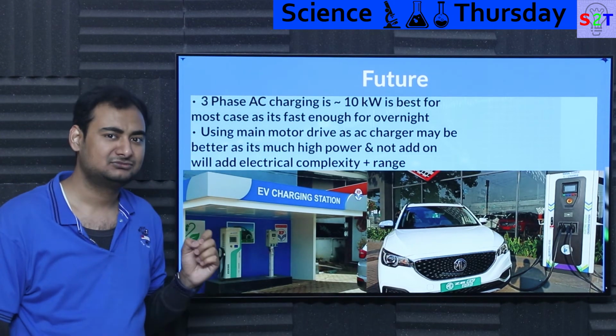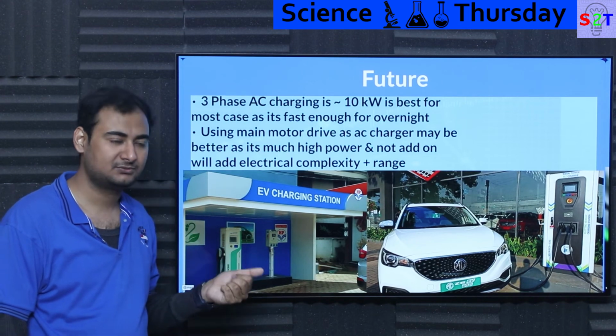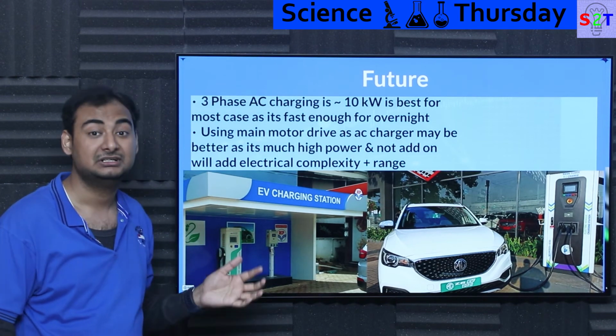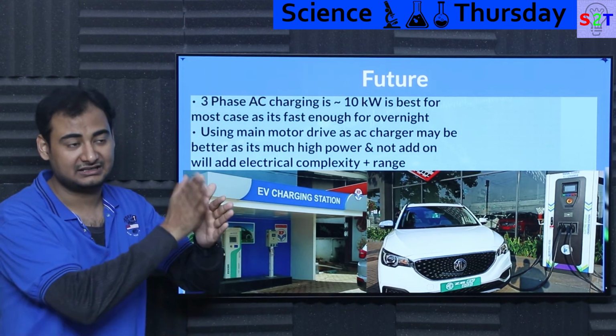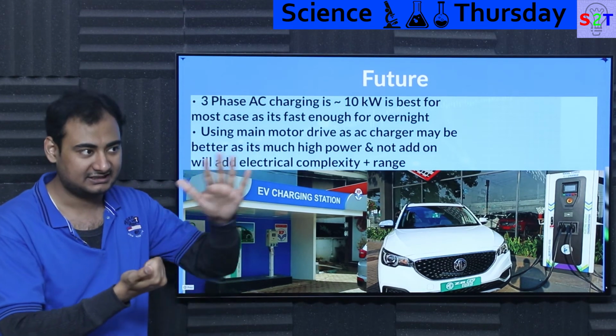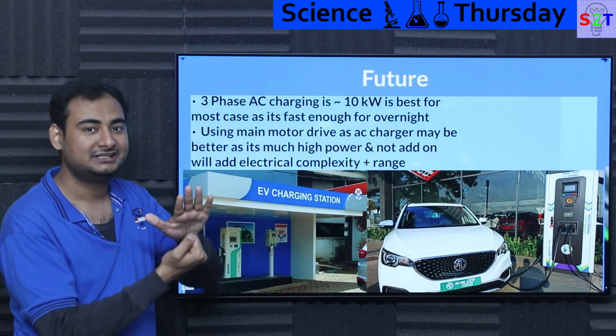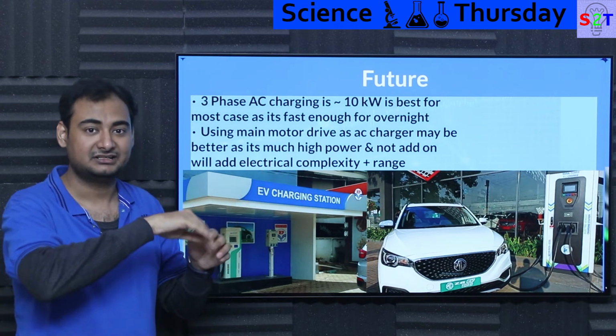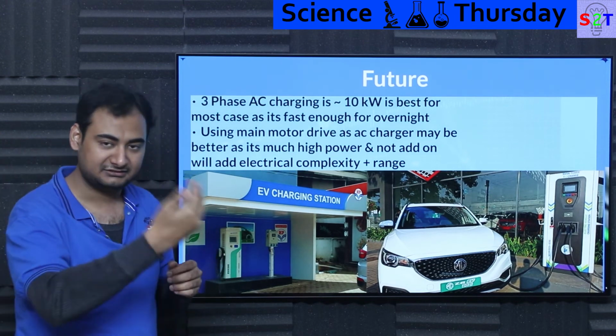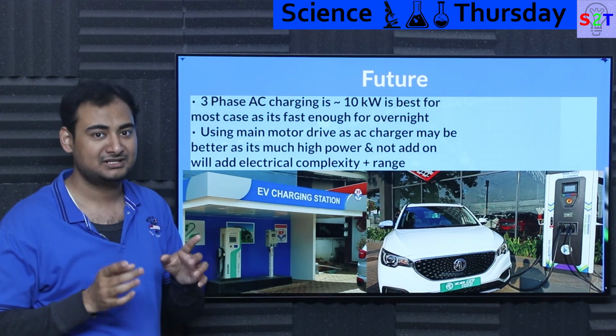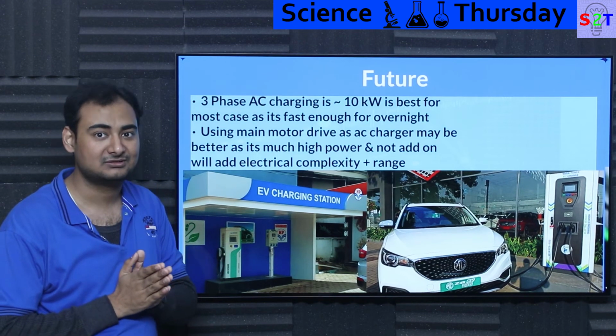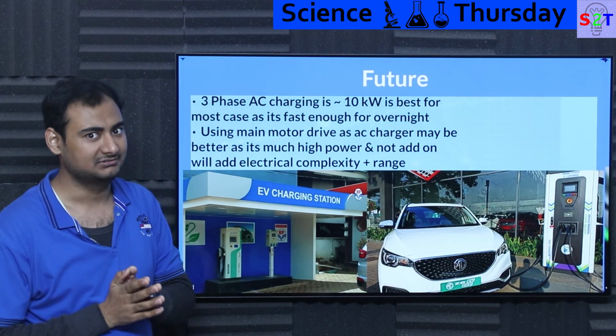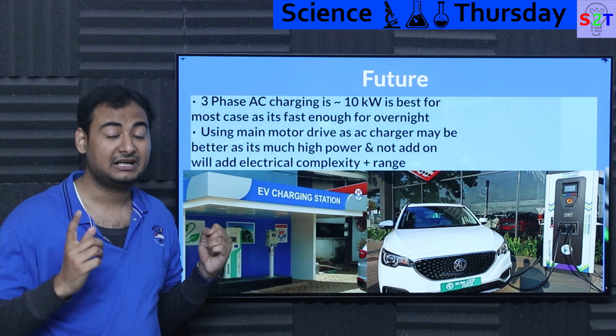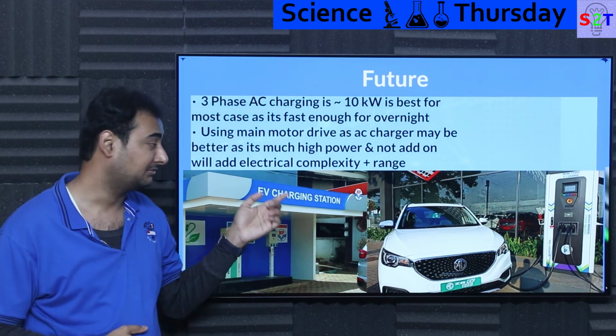So that's one thing that I'm noticing that can be done. I know from a physics point of view, from an engineering point of view, it can be done. But if you know any exact reason why you can't just disconnect the contactors that are capable of handling the motor currents, disconnect it, reconnect it to the AC line, then directly feed the system. Again, it does have to do phase matching. It will require a different level of microcontroller processing, but it should be doable.